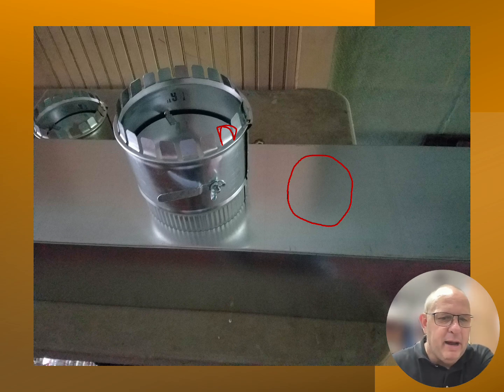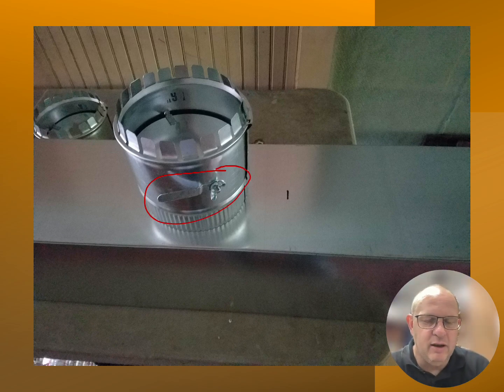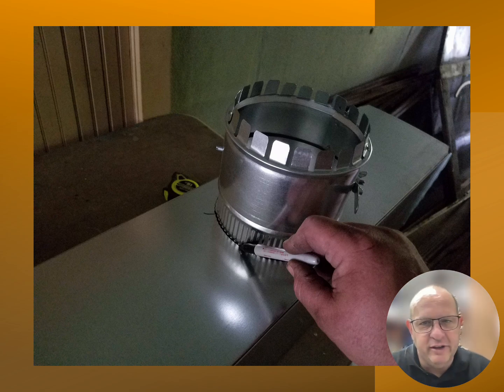But a couple of things to understand about what we're seeing within this picture. So this is a round takeoff, and on the inside of the takeoff, we have a damper. This is what you need to know about every unit that you go to install: when we are taking off from the main trunk, we should install a damper in it in order to adjust the CFM values going into that particular branch. Installing the damper is as easy as drilling a hole into the takeoff that's sitting there. I'll drill a hole on one side, and there are a lot of different dampers out there, and I'll drill a hole on the other side, and then I'll insert that damper, or that air volume control, into the takeoff itself.